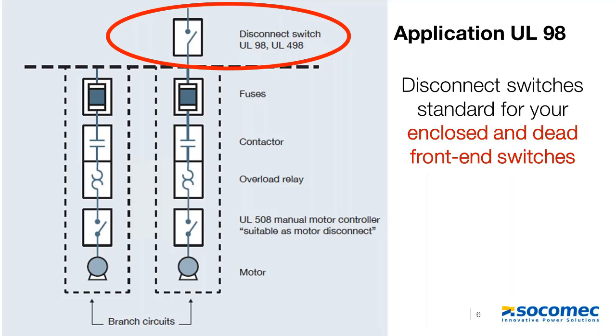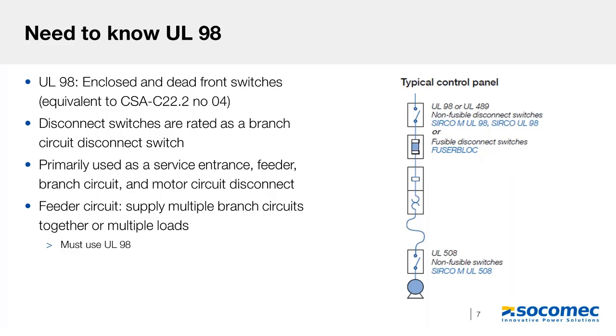The first is the UL98 standard, which you can see is circled at the top of the circuit. And to get into those details, the UL98 is the standard for enclosed and dead front switches. The switches with this standard are primarily used as service entrance, feeder, or branch circuit disconnects. However, these switches can also be used for motor disconnect applications as well.